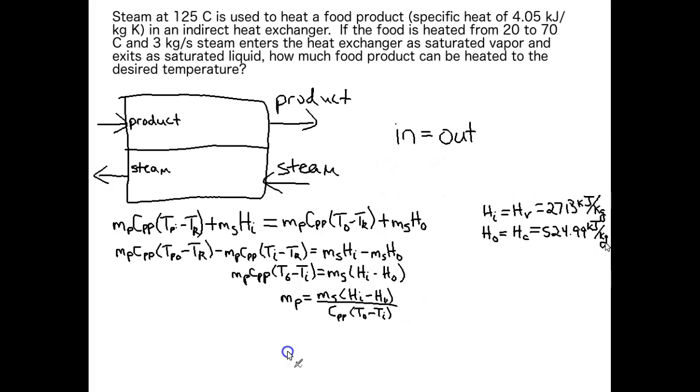Now that we have all our numbers, let's go back to our equation for the mass of our product, plug everything in, and see what we get. And there you have it—we can heat almost 32 and a half kilograms per second of product with this amount of steam.